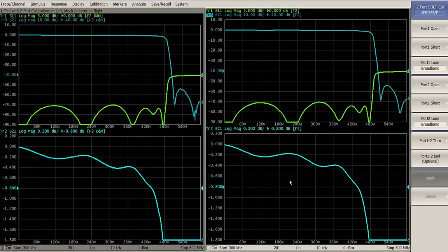So now we are ready to measure the filter and compare it to the LPAD results. And I would say, just by looking at this, that the results are identical. Even though I said there could be more transmission tracking error due to the poor raw source and load match, due to the 50 ohm source and load in a 75 ohm system, I'm not actually seeing the effects of that. So I think that's a worst case prediction. I think for the most part, if you use the mechanical adapters, you're going to be fine, and you'll get good measurements. Particularly if, as one customer needed, you must measure up to 12 gigahertz, using 50 ohm cables that were capable of measuring 12 gigahertz, and putting the mechanical adapters on the end of the cables.